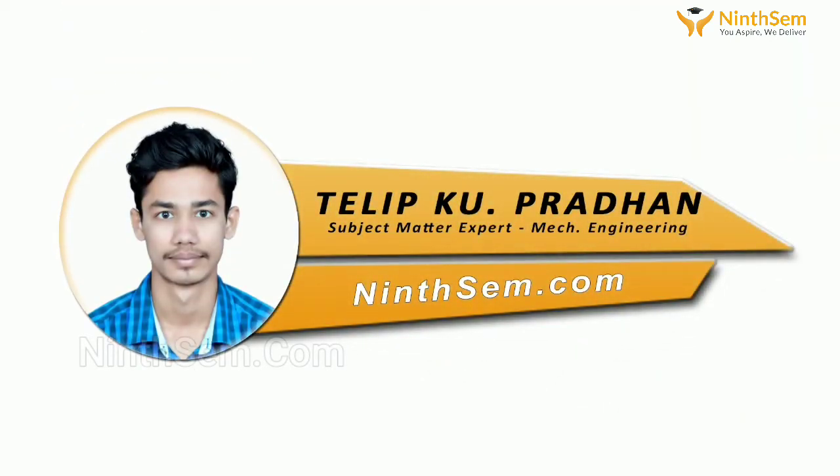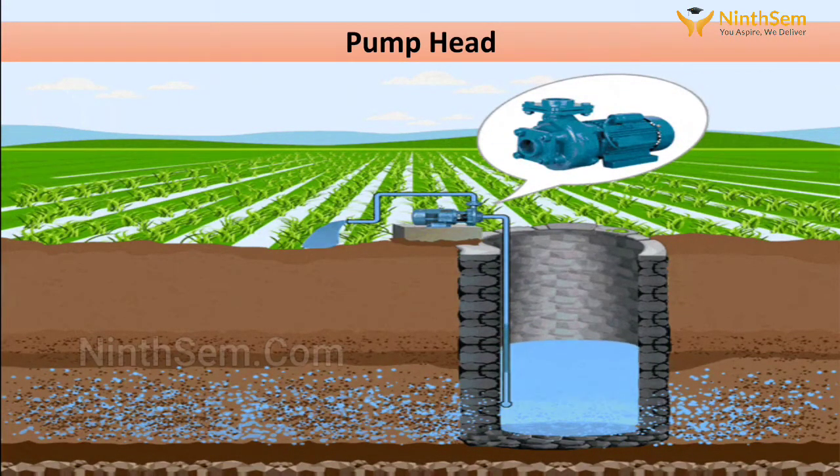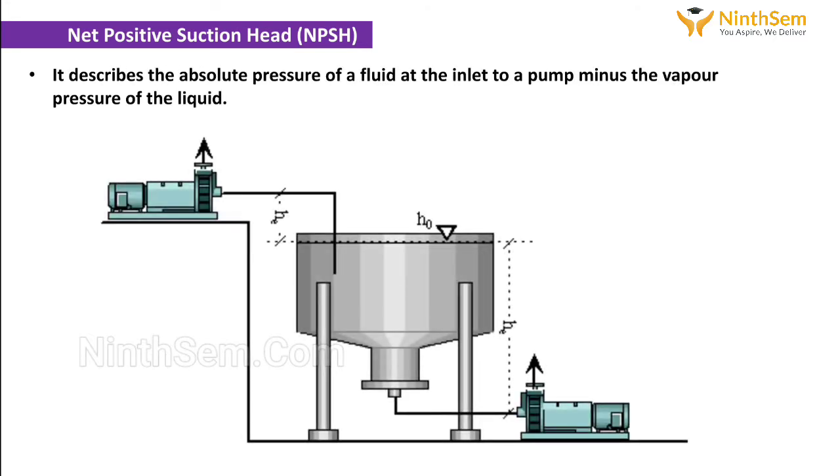In this video, we are going to discuss some pumping terms like NPSH, which is net positive suction head, and pump head. So let's discuss what is NPSH. The full form of NPSH is net positive suction head. NPSH is the term that is usually used to describe the absolute pressure of a fluid at the inlet to a pump minus the vapor pressure of the liquid.